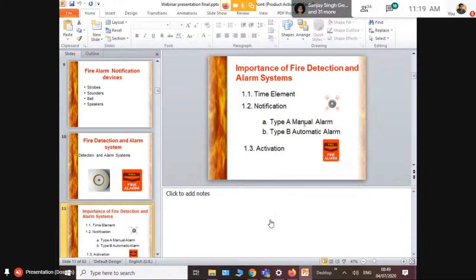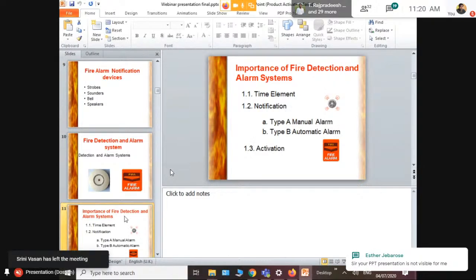So the types of alarms we are notifying here: type A is manual alarm, type B is automatic alarm. Manual alarm is something which is initiated manually, so that is where the break glass comes into action. You pull it by yourself, you are notifying the control panel that there is a fire, so it's called manual alarm. Type B is an automatic alarm, which is initiated automatically by the smoke detector itself. Okay, and this is how the activation happens.